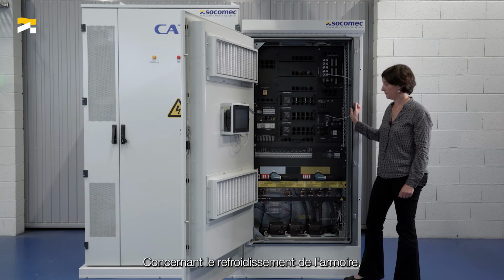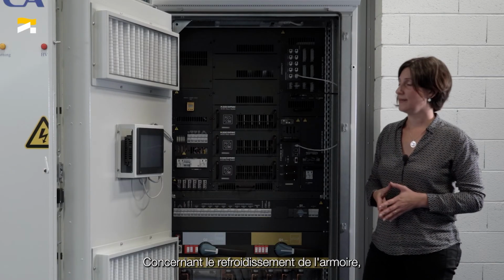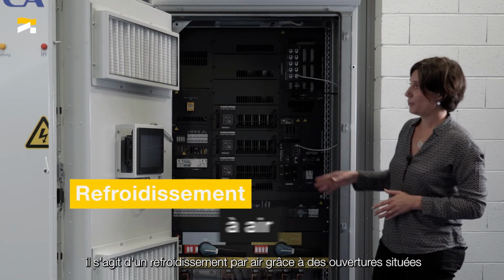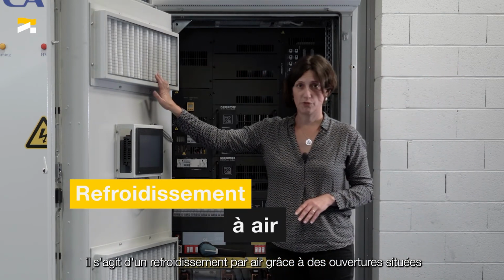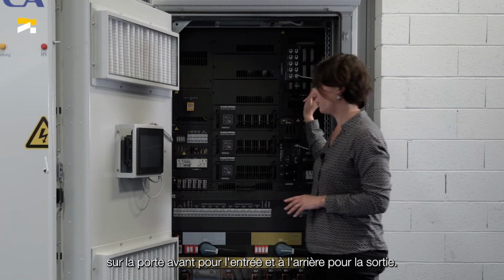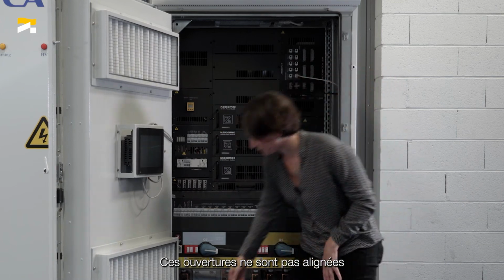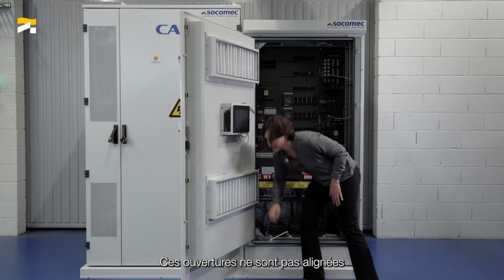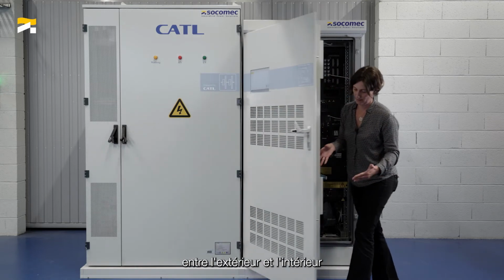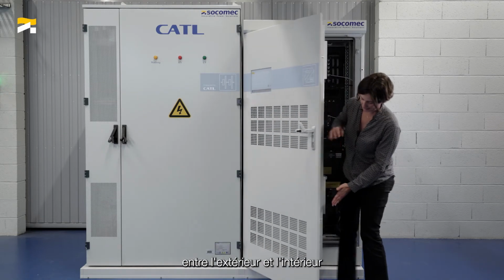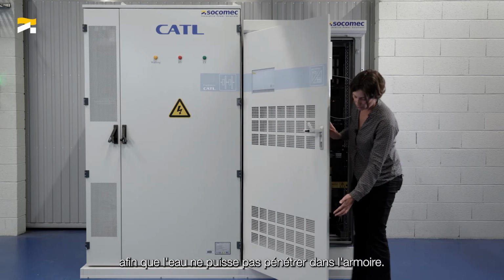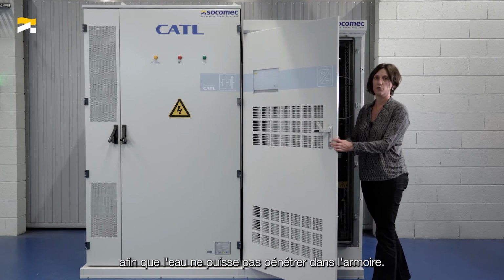Concerning the cooling of the cabinet, it is air-cooled through openings that are located on the front door for the inlet and at the back for the outlets. These openings are not aligned between the external and the internal, so that no water can enter into the cabinet.